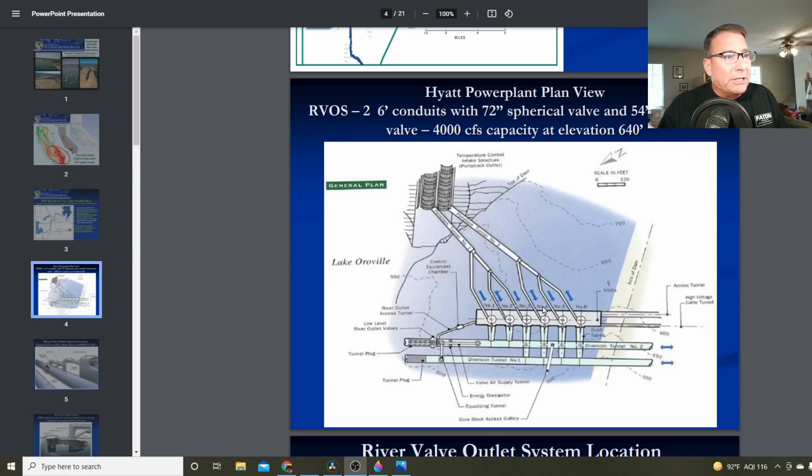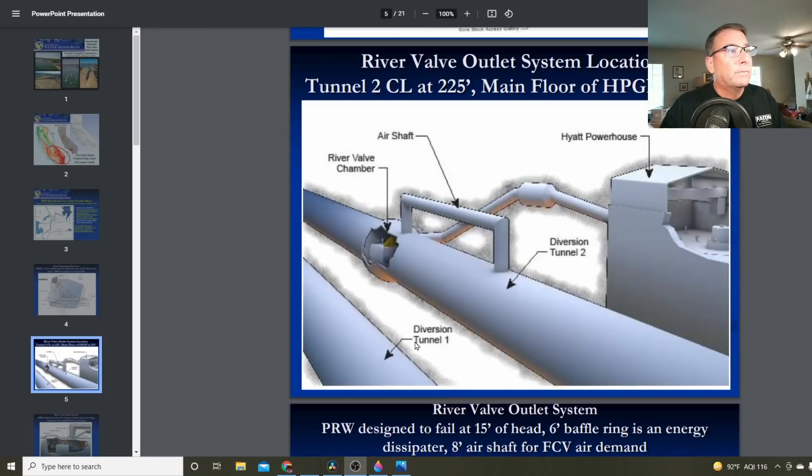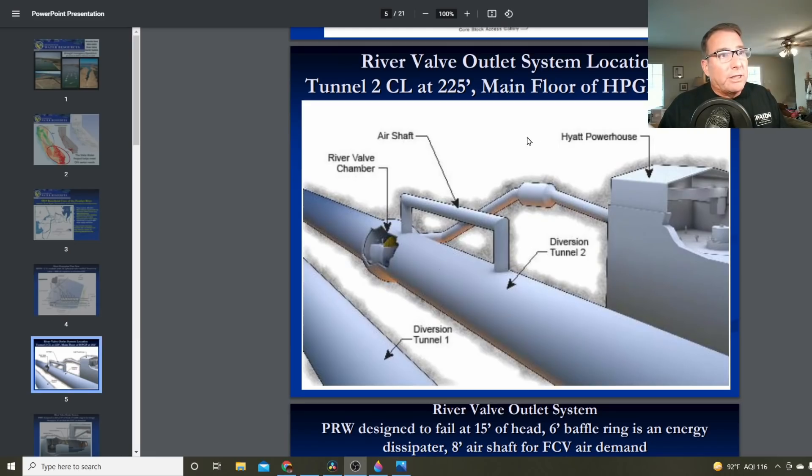Those turbines discharge through the two diversion tunnels — number one and number two. These were the tunnels put in when they initially built the Oroville Reservoir. Inside diversion tunnel number two is the river valve outlet system. Now, nearly at the bottom of the reservoir, this is the last way to get water out of the Oroville Reservoir. The river valve outlet system goes all the way down to an elevation of nearly 225 feet.